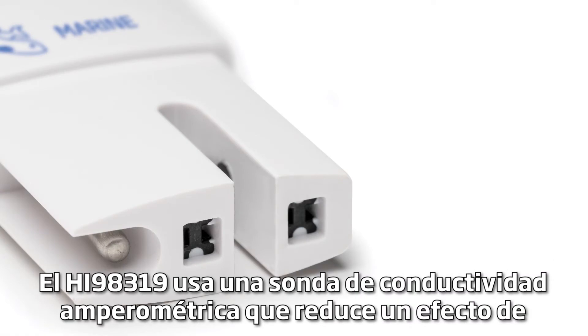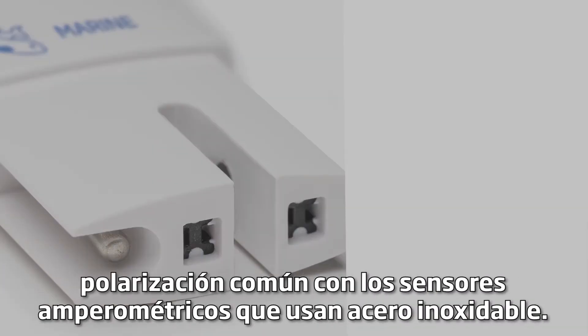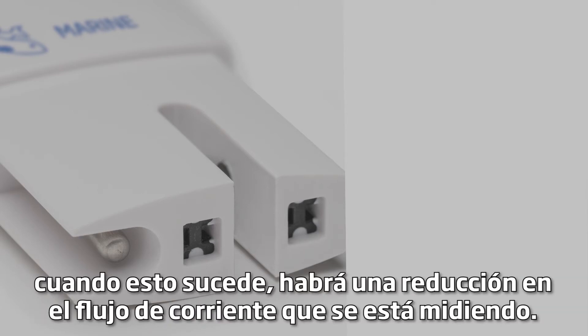The HI-98319 uses an amperometric conductivity probe, which reduces the polarization effect common with amperometric sensors that use stainless steel. Polarization causes a charged ion buildup on the surface of the electrode, which results in a reduction in the current flow being measured.